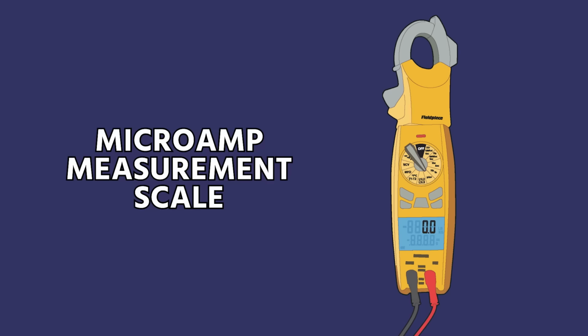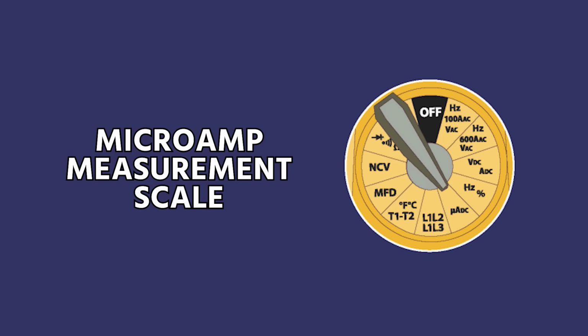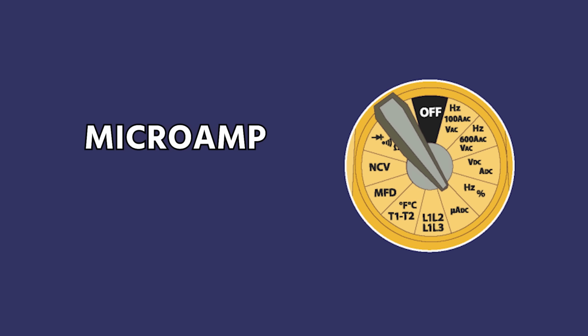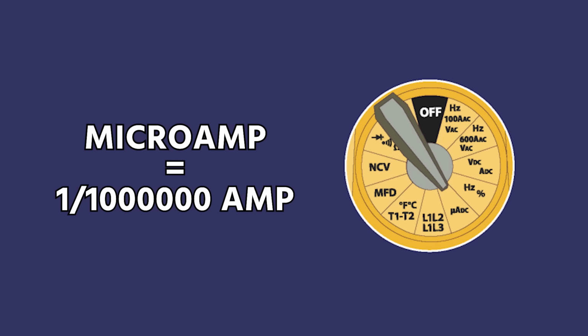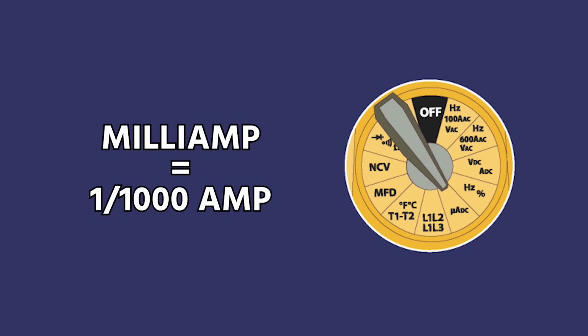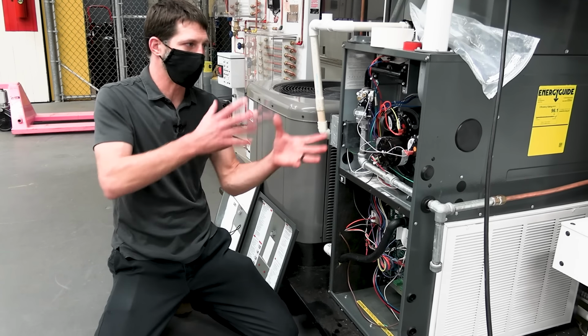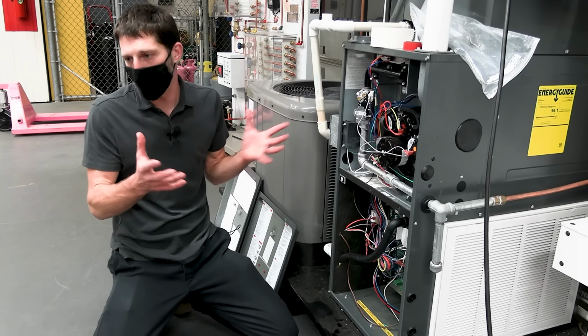And your meter has to have a microamp measurement scale. It's not milliamps. It's not the same thing. Microamps is a millionth of an amp, not a milliamp, which is a thousandth of an amp. A lot of times people try to correct me and say that it's supposed to be milliamps, and it's not. It's micro.